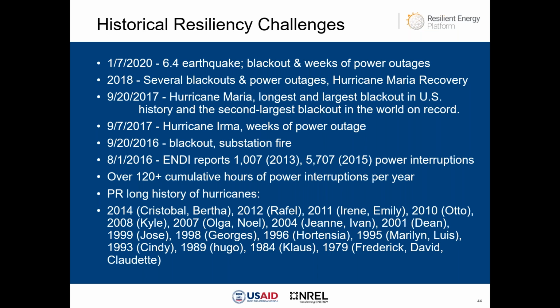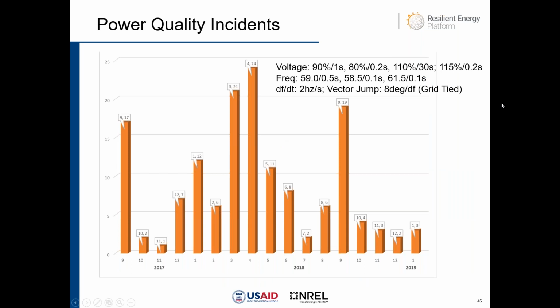In a good year in Puerto Rico, a typical generator will run at least 120 hours per year, and there have been several occasions when customers have exceeded the 500 hours per year limit established. This leads to the inevitable unreliable power and low power quality. This chart shows the power disturbances measured from the grid intertie protection relay in the CHP plant at San Germán for about a year. Some months, up to 24 events were registered, almost one per day. The events were triggered by wide voltage and frequency fluctuations, a deviation of about plus or minus 1 hertz and about 10% on voltage. This type of power quality deviation caused damage to equipment of many PREPA customers.